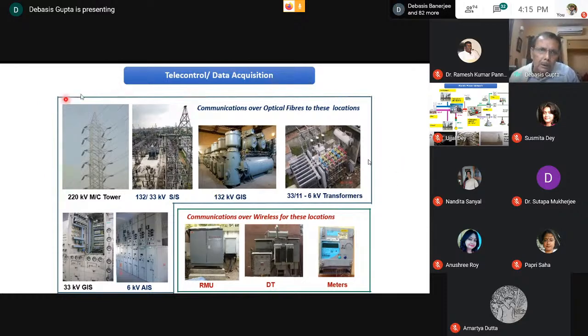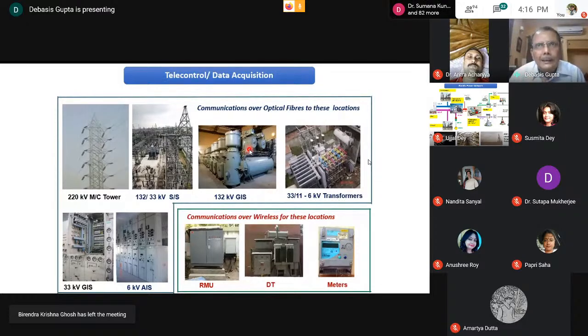There, because you are using protocols like IEC 104, which are very tight, it can't be on a best effort basis. When you want to switch on a breaker, it has to switch on within 2 seconds, finish, or 1 second, as you specify. So there, the general tendency is to use MPLS networks. In Calcutta, mainly fiber optics is used, also in parts of Delhi and other metros. Some telcos are offering dedicated bandwidth and dedicated lines on MPLS, which are working across India.